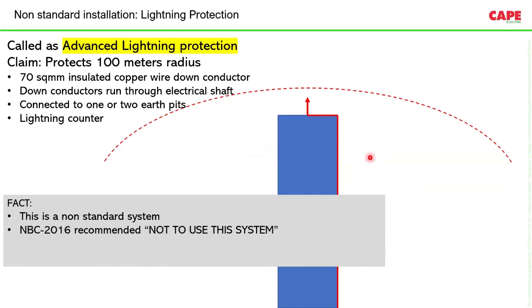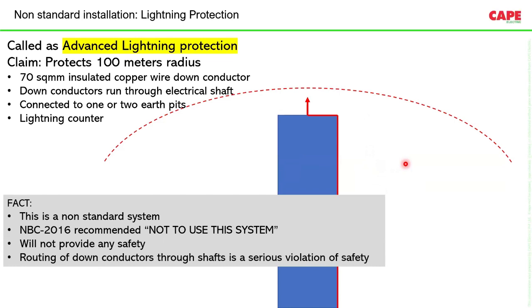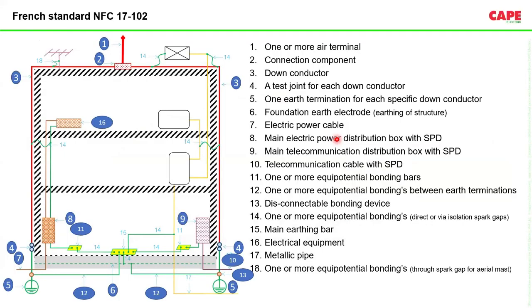National Building Code 2016 recommends not to use this system. It cannot provide any safety, and routing down conductors through a shaft is a serious violation of safety. Now, as an argument, these manufacturers and suppliers claim that this is as per the French code. It is as per the French standard. Then users sometimes believe that the French standard is also a good standard, so let us follow it. But please note that the French standard is not asking for one down conductor and one earth electrode.